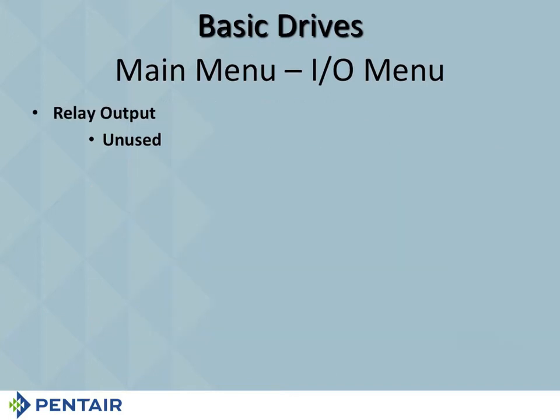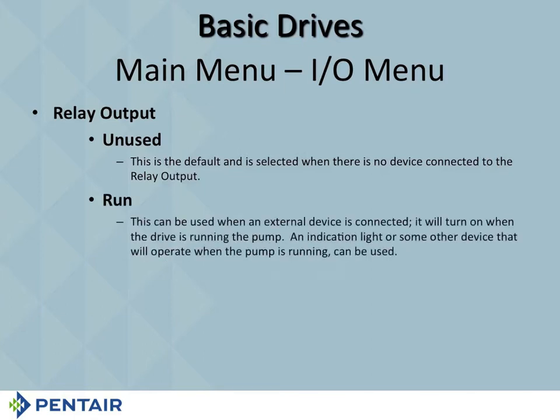All right? Now, outputs, there's 3 things you can do with an output. It's going to come unused. That's the first thing you do, just leave it unused. You can use it for run. Run means that when the drive turns on, I want the output to close and turn something else on. It can be hooked up to a light, and so the dry contact closes and sends a signal to that light and turns that light on. It can be hooked up to another pump via a pump start relay. In other words, you cannot run the other pump from the drive, but you can tell the other pump to turn on with the drive. So you put this in run, and when it closes, it sends a signal to a pump start relay that will close, that turns the electricity onto the other pump. All right? And of course, when the pump stops running, the electricity goes away and the relay opens up.